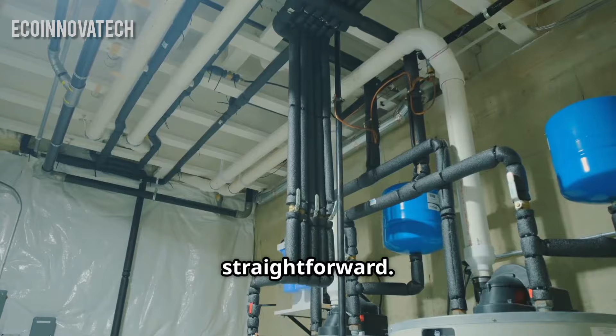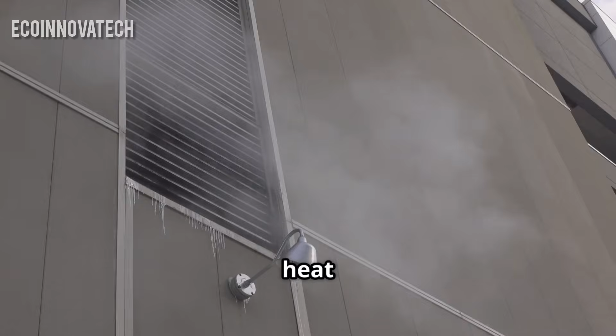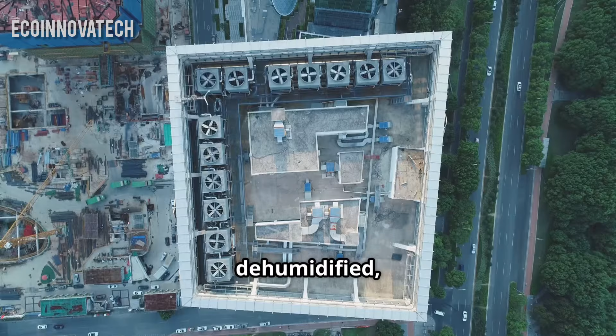Inside each building, the process is remarkably straightforward. The chilled water from the district network flows into the building's own internal cooling system, typically at an energy transfer station. Here, it passes through a heat exchanger, which transfers the coolness to the building's own water loop. This secondary loop then circulates to air handling units, or AHUs. As warm air from inside the building is drawn across the coils filled with this chilled water, a simple heat exchange occurs. The air is cooled and dehumidified, while the water absorbs the heat.